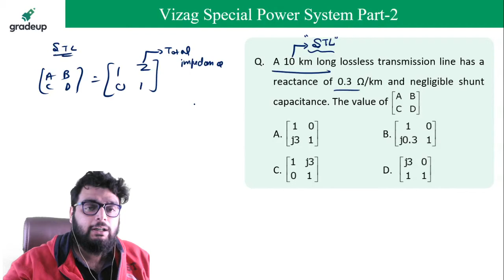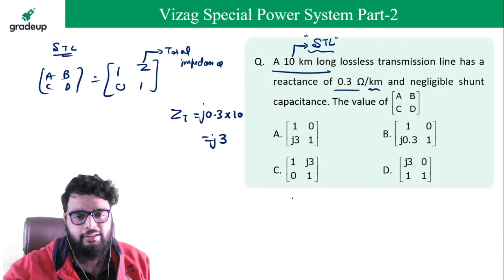Okay, so C option is given by some people. Let's see. In case of a short transmission line, what is the formula of ABCD parameter? The ABCD formula is very simple. A very simple formula. 1, 0, 1, Z, where Z is the total impedance. So it is given for the line you have impedance or the reactance of 0.3 ohm per kilometer. So what will be the total impedance? It will be 0.3 multiplied by 10. Why? It is given per kilometer. It comes out to be j3 because of reactance. Option C. Good. Next one.